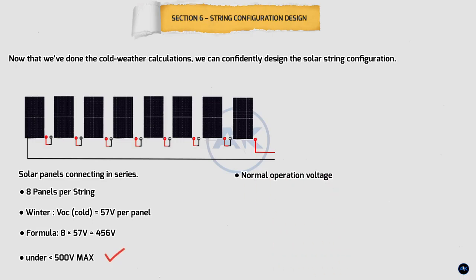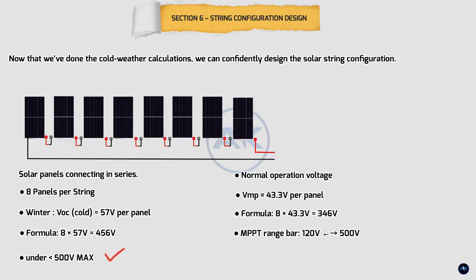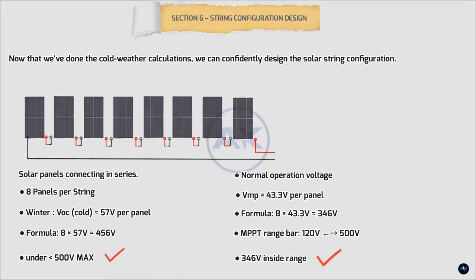Now let's check normal operating voltage, also called VMP. Each panel has a VMP of 43.3 volts. 8 panels in series gives us 8 multiplied by 43.3, which equals about 346 volts. This value sits comfortably inside the inverter's MPPT operating range of 120 to 500 volts. That means the inverter can track power efficiently and operate without stress. So, to summarize, cold weather VOC safely below 500 volts, operating VMP well inside the MPPT range. This confirms that 8 panels per string is the correct and safe configuration for this system. In the next section, we'll connect these strings to the inverter's MPPTs and calculate the total system power.